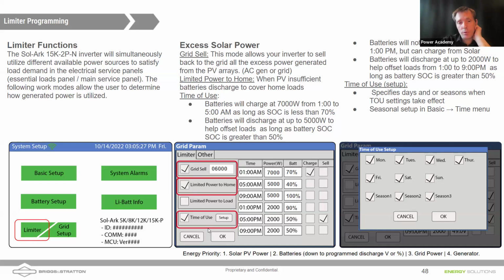But to get to the question, if we enable time of use here and you click the setup, it allows you to choose what days of the week or even set up seasons for time of use. And what we're going to do with time of use is control the use of energy stored in the battery. If we enable charge, that allows the battery to charge when it's below the threshold of 70% state of charge. If we click the sell box here, it allows the battery to sell excess power to the grid.